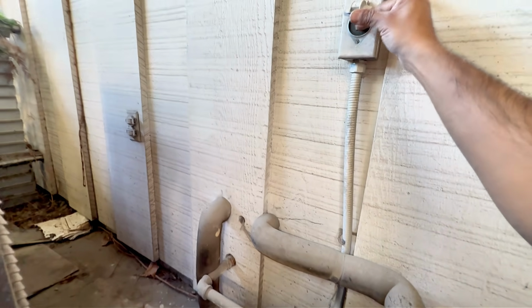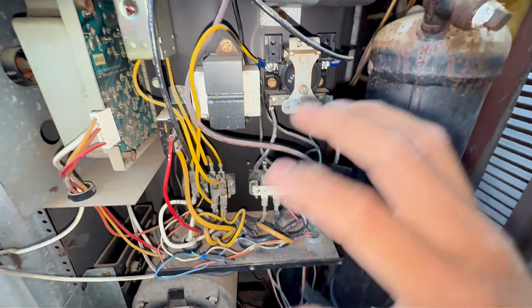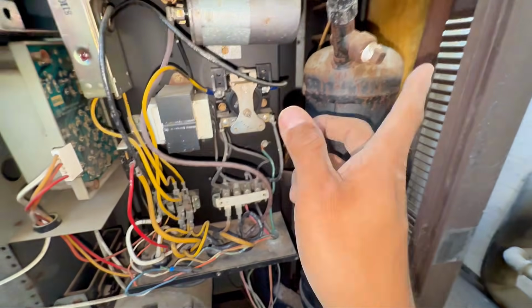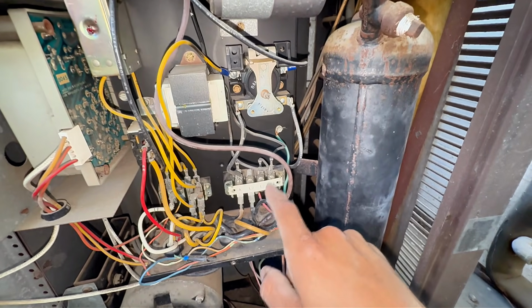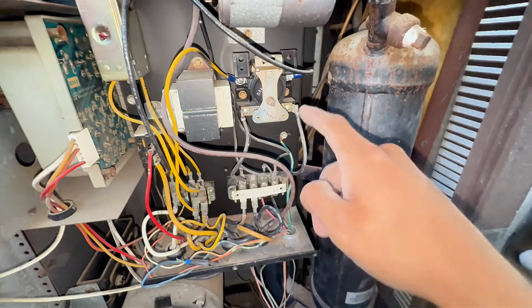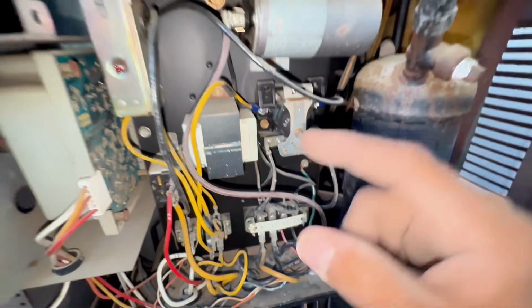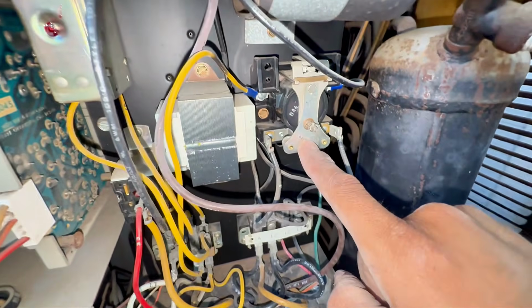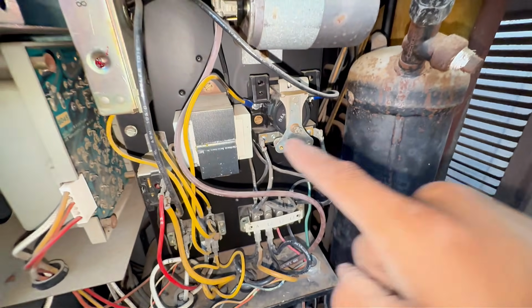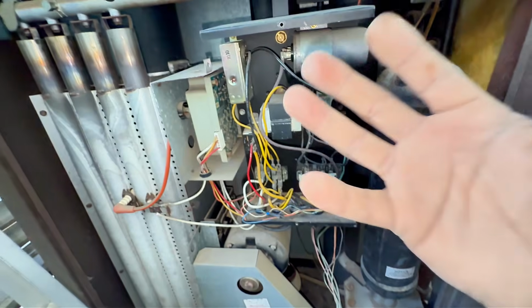Let me show you. I'm going to make sure power is off, right? I'm going to turn off power just to show you. Remember the contactor, and I had already confirmed this earlier with power off. I did check that I was not getting power between line 1, line 2, and then line 1 to ground, line 2 to ground. But you see, all this is just a switch. So it's just like a contactor. You push it, like a push button, and then power goes from here to here, and then powers everything up. Same concept, right?